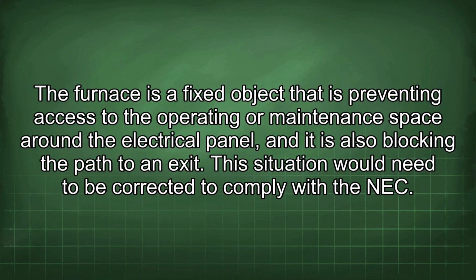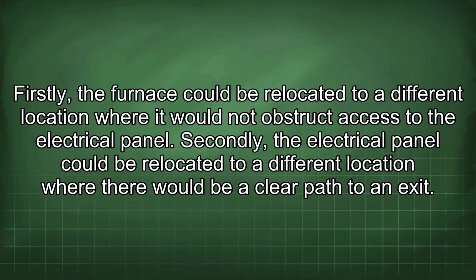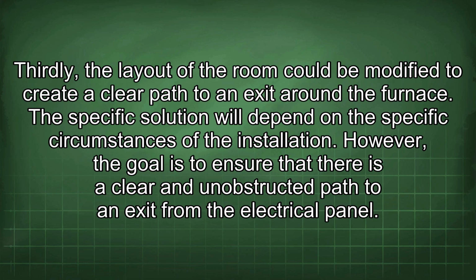The furnace is a fixed object that is preventing access to the operating or maintenance space around the electrical panel, and it is also blocking the path to an exit. This situation would need to be corrected to comply with the NEC. Firstly, the furnace could be relocated to a different location where it would not obstruct access to the electrical panel. Secondly, the electrical panel could be relocated to a different location where there would be a clear path to an exit. Thirdly, the layout of the room could be modified to create a clear path to an exit around the furnace. The specific solution will depend on the specific circumstances of the installation.